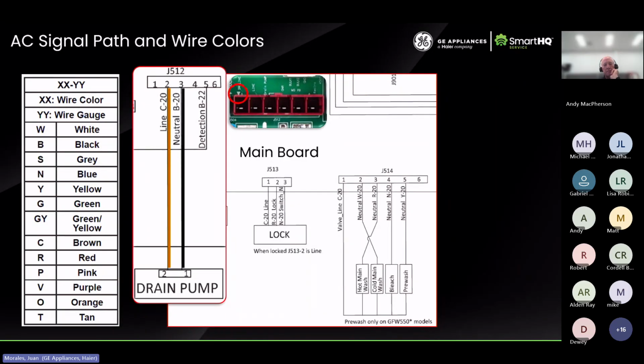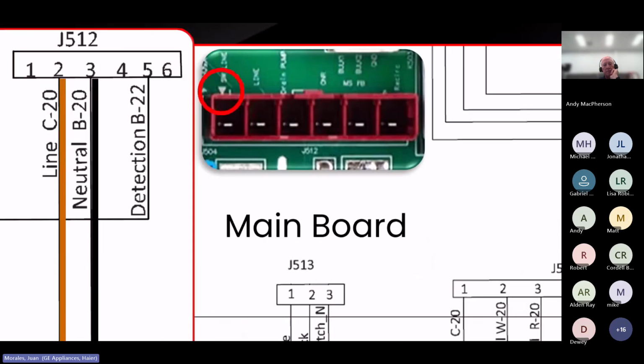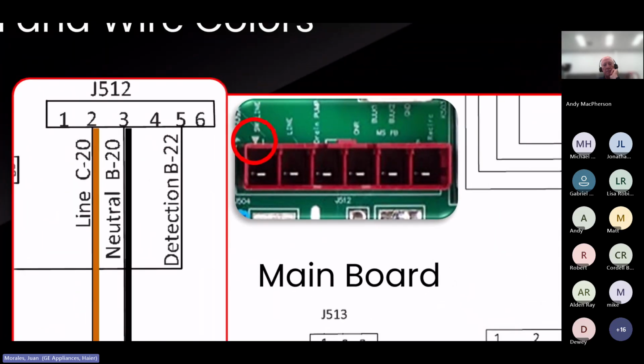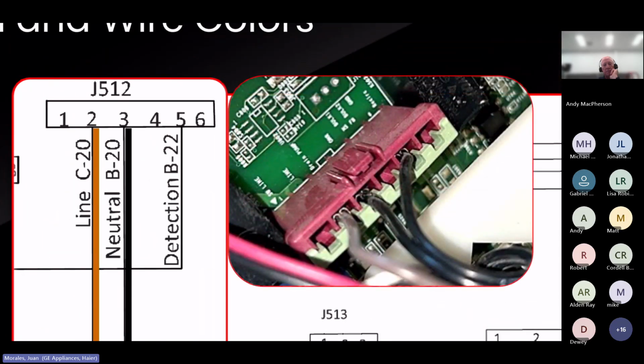Now, in your world, it is not going to look empty like this. In your world, it is going to look like this. You're going to have the connector, and there's your pins number 2 and 3. If you wanted to measure voltage coming from the main to the drain pump, which is probably the easiest way to troubleshoot if you're getting power to the drain pump, you just put your multimeter leads between the brown and the black wire, the ones next to one another, and voila, you should get 120 volts. Now, how are you going to activate that drain pump?